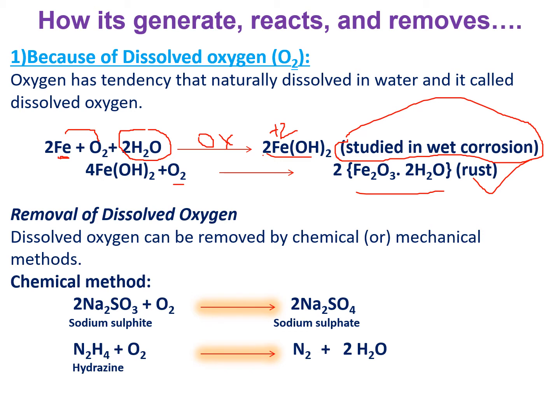How can we remove this dissolved oxygen? By adding sodium sulfite (Na2SO3) to the water to absorb the dissolved oxygen — it produces sodium sulfate (Na2SO4). Two moles of sodium sulfite absorbs one mole of oxygen and forms two moles of sodium sulfate. Another method is by adding hydrazine: it produces nitrogen gas and water. Adding hydrazine is the best option because we produce inert nitrogen gas, which will not affect any boiler material. With sodium sulfite, you are removing oxygen but creating sodium sulfate, which can cause sludge or scale problems.